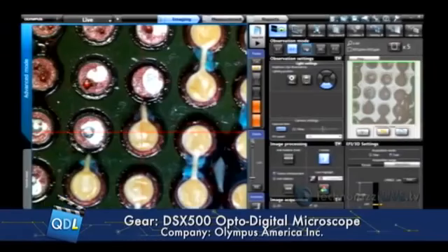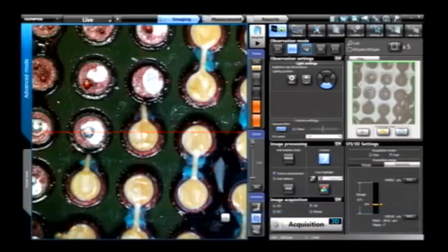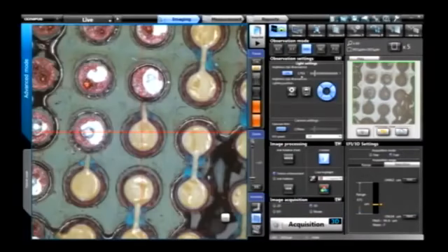When we have a new feature, something unique to our tool here is mix. This allows us to not only use dark field lighting, and we still have our segmented LED here, but it allows us to incorporate the bright field observation at the same time. It looks like you're going to adjust the bright field as you need. Exactly. So you can turn your bright field observation a little brighter or darker to get your background image that dark field usually cuts out, but still get all the edge enhancements of dark field. One observation modes, single push button.